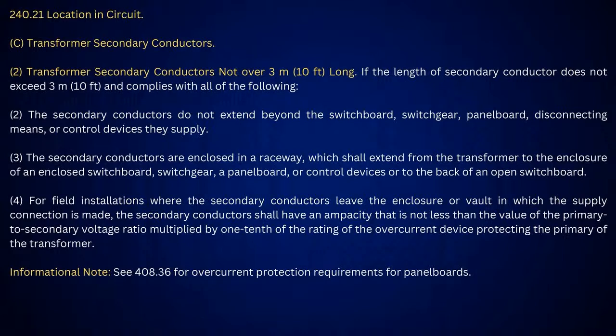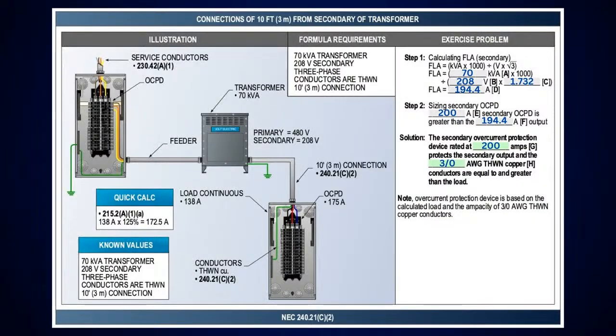Okay. And you come in here. If I look at field installations in 4, it goes in the vault in which it supplies, and so on. It says it shall have an ampacity that is not less than the value of the primary to secondary voltage ratio multiplied by 1/10 the rating of the overcurrent protection device. So you come in here, I've got to get that. And if I'm going to come on that secondary side, you'll see I've got to get what the transformer rating is for that secondary side.